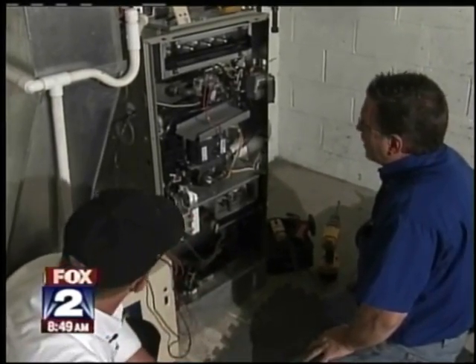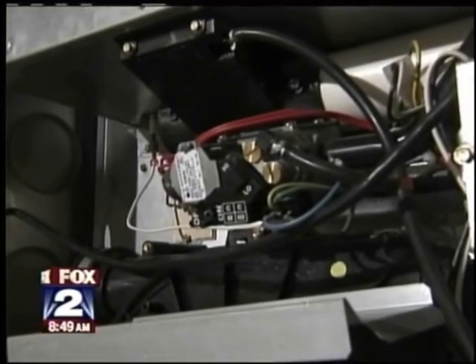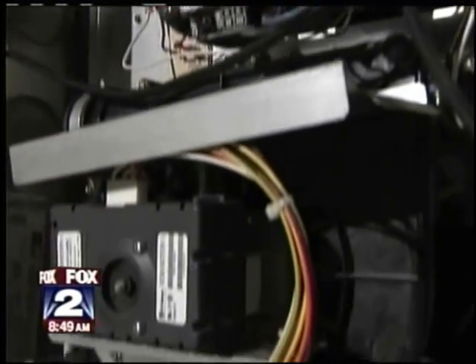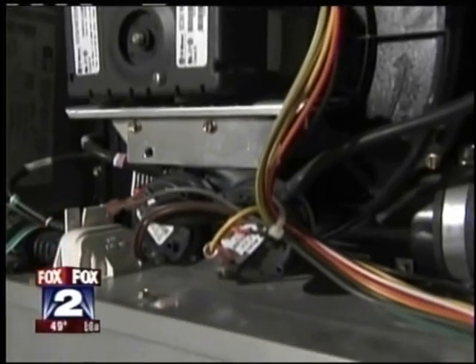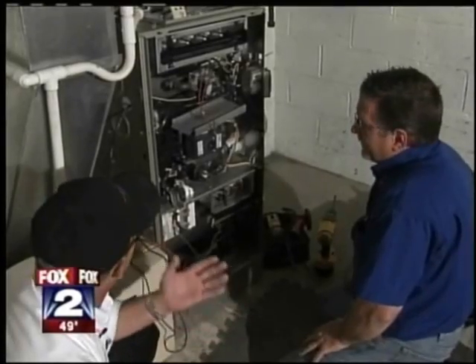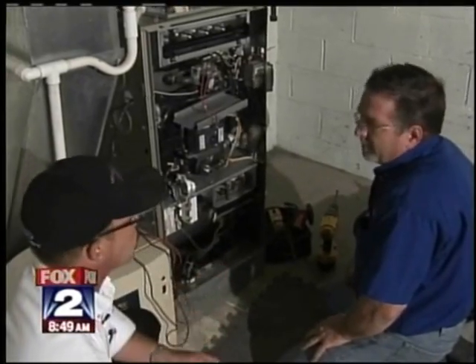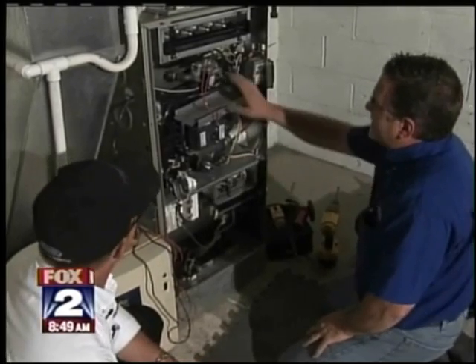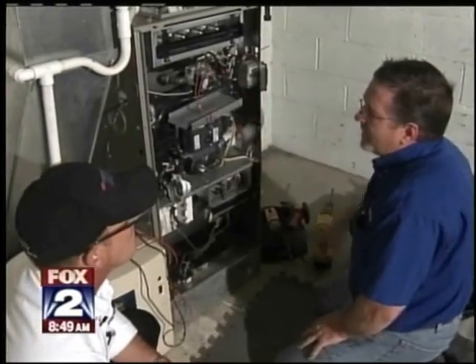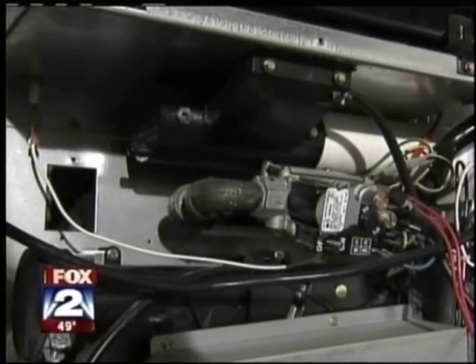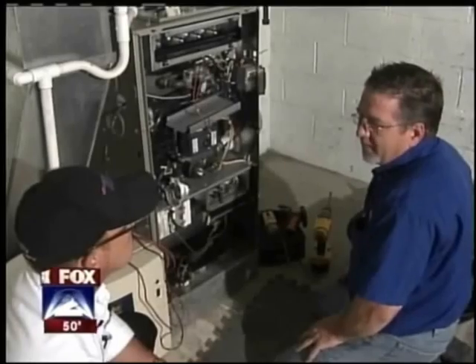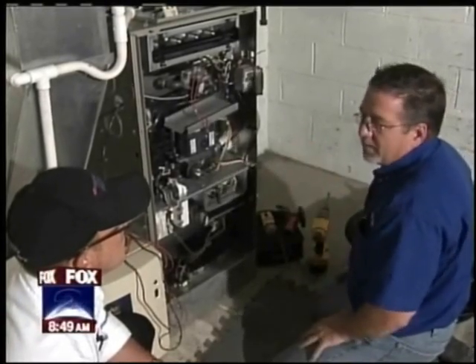What else do you do on the furnace? We check the amp draws on everything, making sure all the motors are within tolerance for how many amps they're drawing. How about gas pressure — is that important? Very important. As equipment gets older it falls out of spec, so we check that every year to make sure it's right where it needs to be.